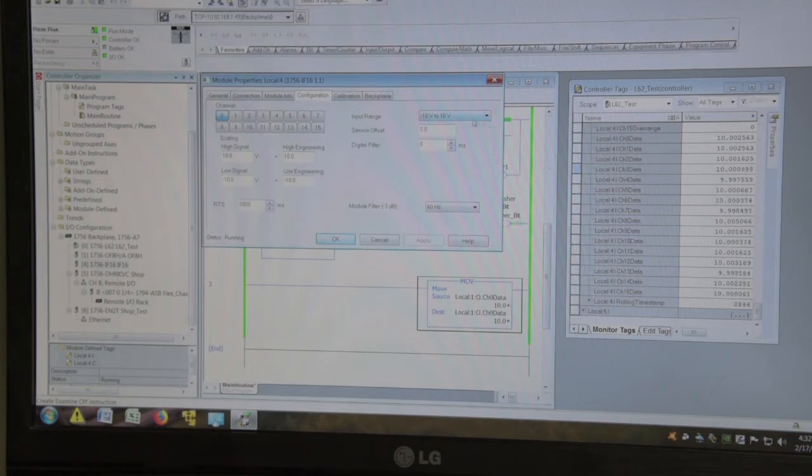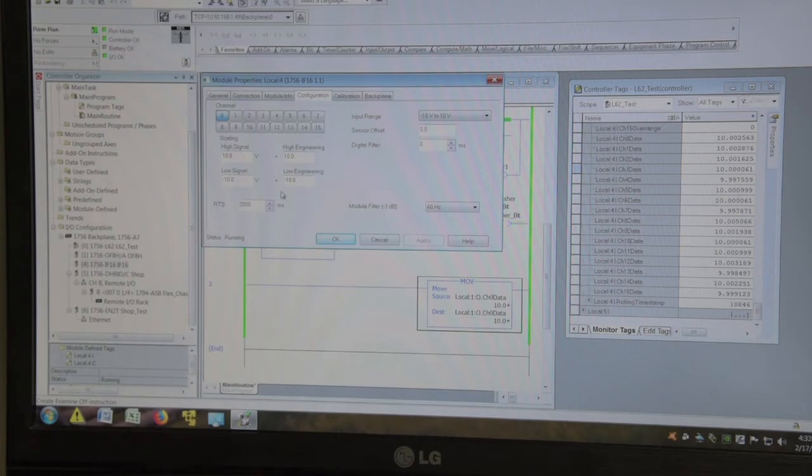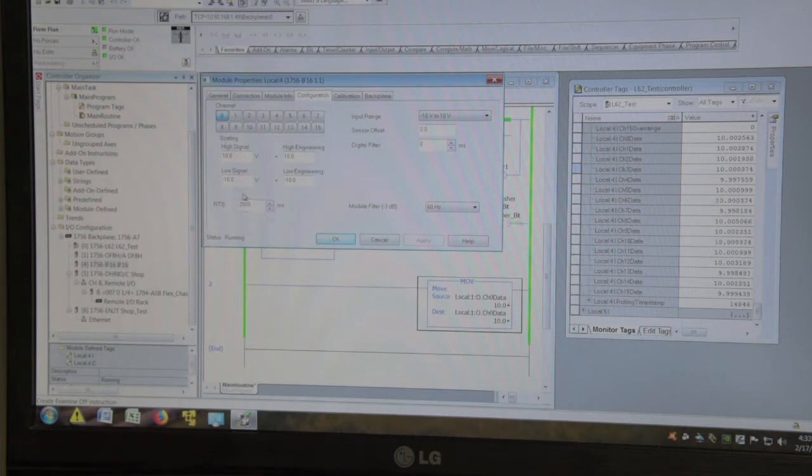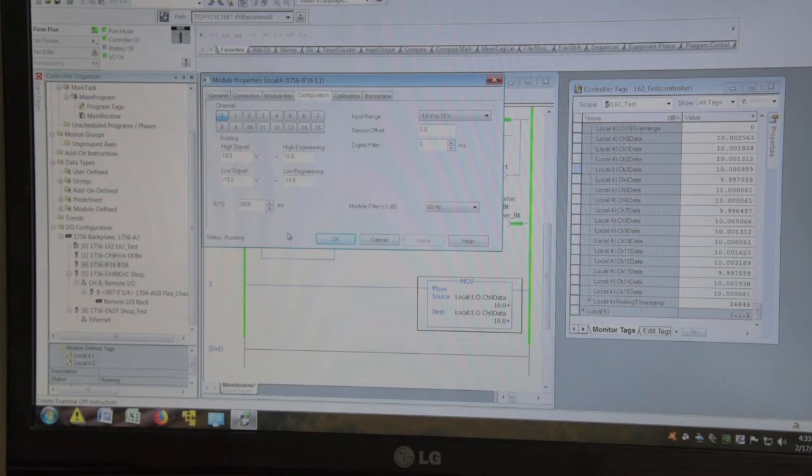All 16 channels are configured the same way. Plus or minus 10 volt. Scaling is plus 10 equals 10 high engineering, minus 10, minus 10 low engineering. And real-time sampling I've set to 2,000 milliseconds just to smooth out the display for testing.